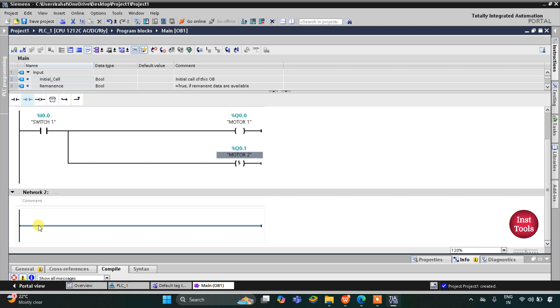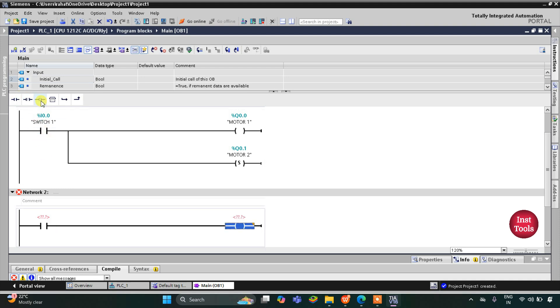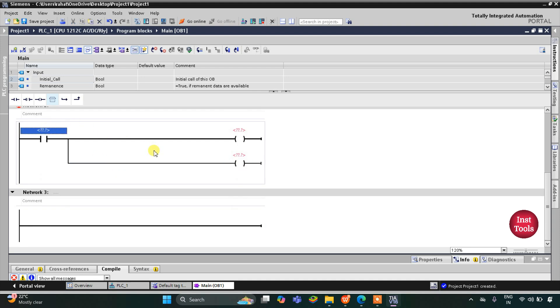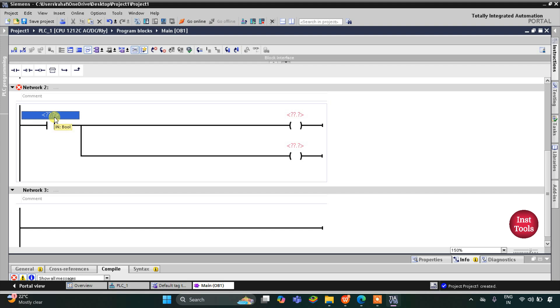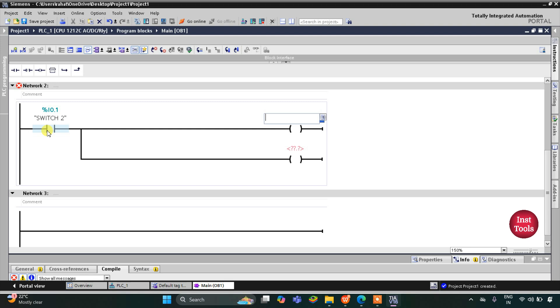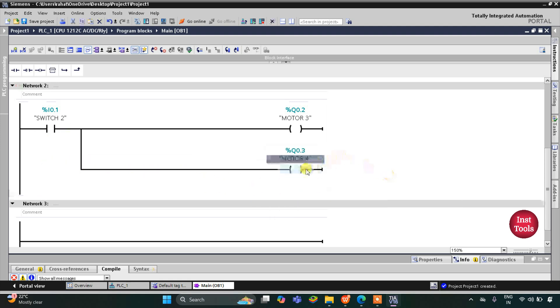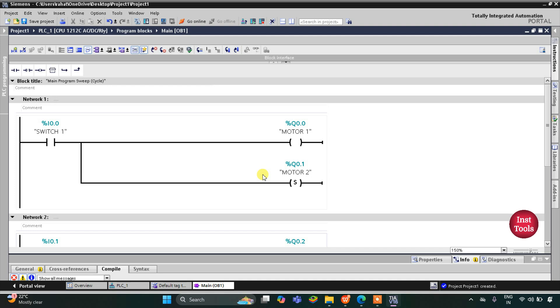Then I will use Network 2 for Motor 3 and Motor 4. There will be one more normally open contact for Switch 2, a coil for Motor 3, and then an open branch to add one more coil for Motor 4. I will select Switch 2 and Enter, then Motor 3, and then Motor 4. For Motor 4 I will choose S from the drop-down list because when Switch 2 is turned on then turned off, Motor 4 still remains on.